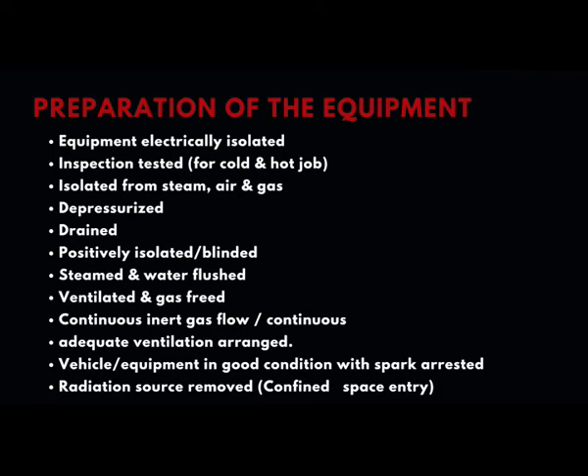Most of the time the system will be under pressure, so it has to be depressurized and vented out. Liquids need to be drained, and the system positively isolated and blinded. For example, in a vessel there will be input lines and output lines, and for both there will be isolation valves.